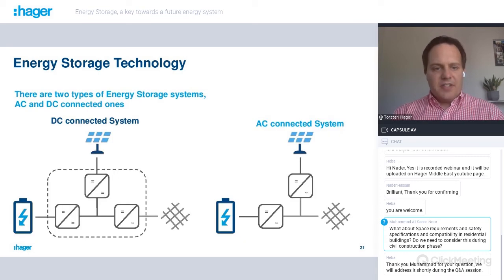For the design of the system, you have two types of battery storage systems. You have DC connected systems, where you have a DC link between the battery, the PV, and the grid - a DC intermediate circuit where all three elements come together and the energy is routed in one or the other direction. Or you have a simpler architecture of an AC connected system, where the battery is directly connected with an AC-DC converter to the network, and your generator, like PV, is also connected with a DC or AC-DC converter to the AC network. If you want to charge your battery, you convert the DC current from your PV to AC and convert it back to DC to charge the battery.